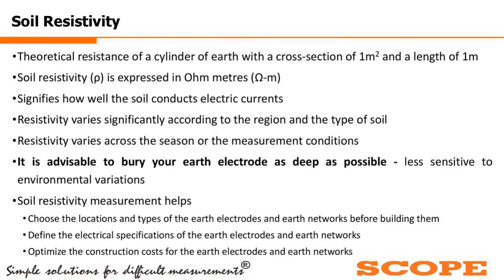Now coming to the soil resistivity. What's the difference between soil resistivity and the soil or the earth pit resistance? Earth pit resistance is the resistance of that specific point where my earth rod comes in contact with the ground. Whereas soil resistivity is not a specific point, it is the value of a specific terrain.